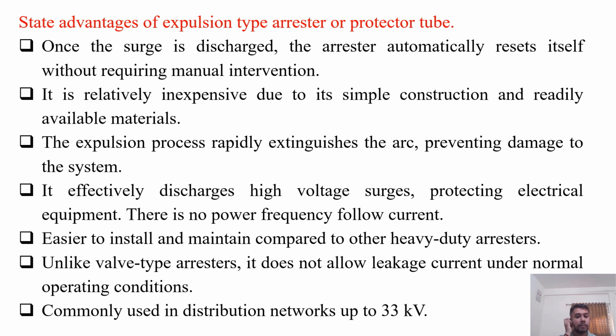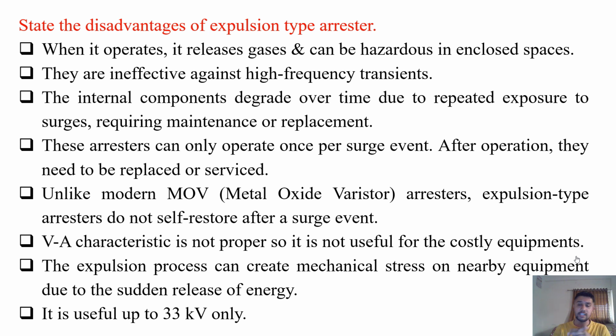Easier to install and maintain compared to other heavy duty arrestors. Unlike valve type arrestors, it does not allow leakage current under normal operating conditions. Commonly used in distribution networks up to 33 kV, so it is highly suitable for the medium voltage system. So these are several advantages of the expulsion type arrestor. State the disadvantages of the expulsion type arrestor or protector tube.